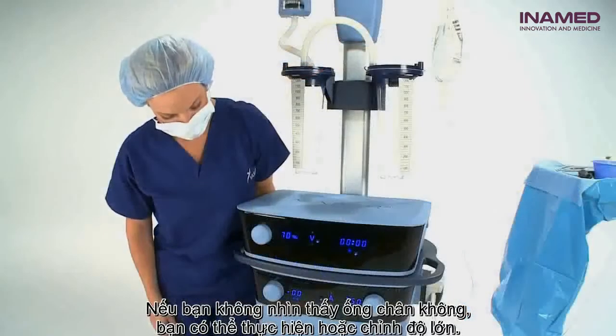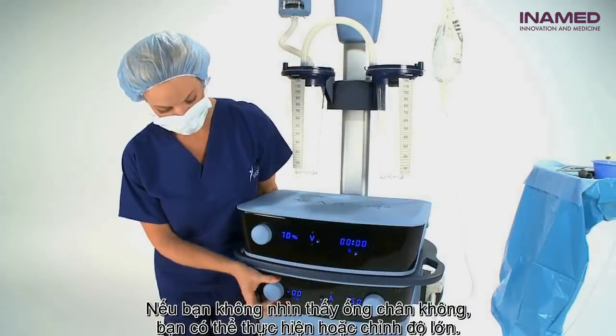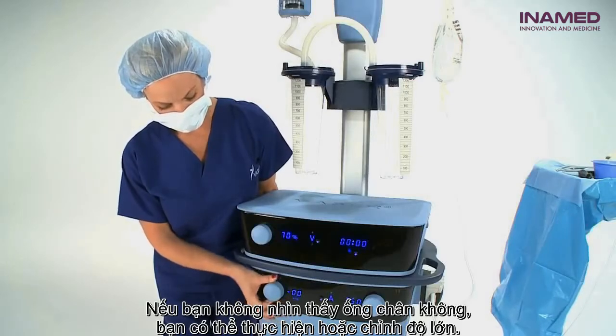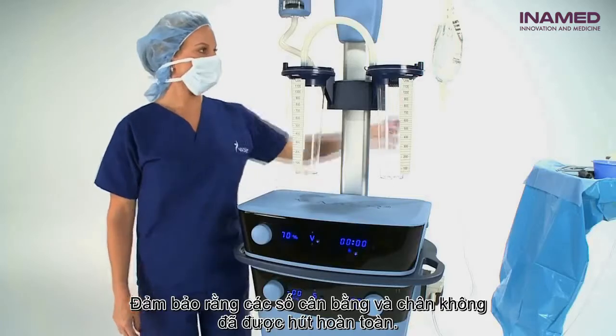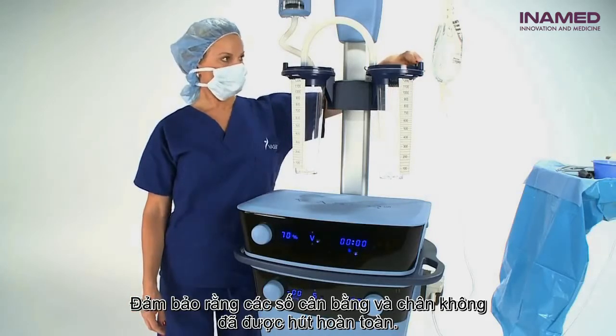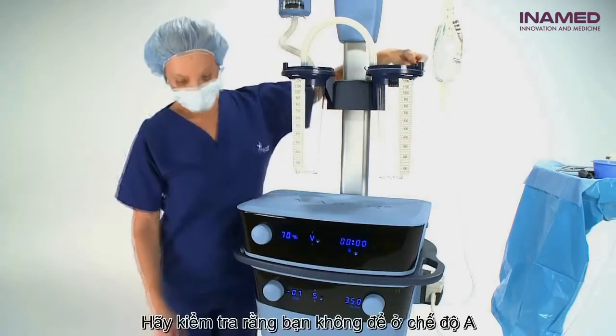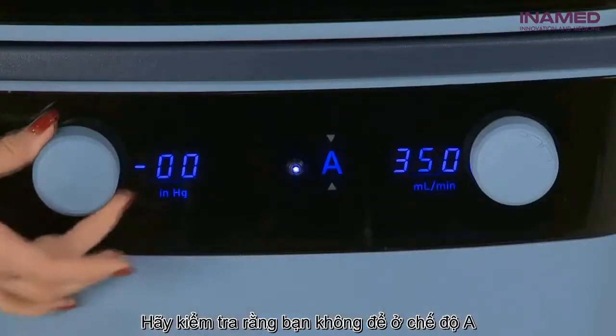If you are unable to see a vacuum ready, you are probably not occluded or the vacuum control is all the way closed. Ensure the dial is turned all the way up, and make sure that the vacuum is completely occluded. Also check to make sure that you are not in ambient mode.